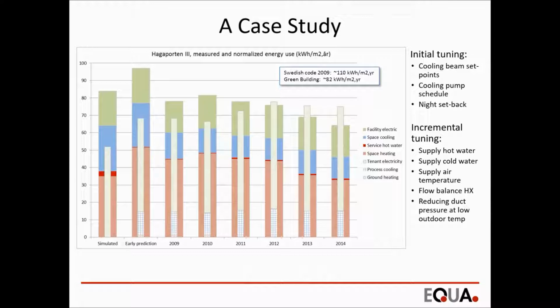So the major reason for this tuning work in this building was that the simulated energy use was quite close to the requirement. It was a green building certified building, and the energy use or the requirement according to the certification system was around 82 kilowatt hours per square meter a year, and also the simulated value was around that order of magnitude. So we didn't have much margin built into this project.